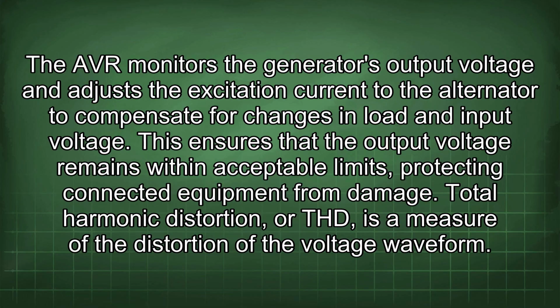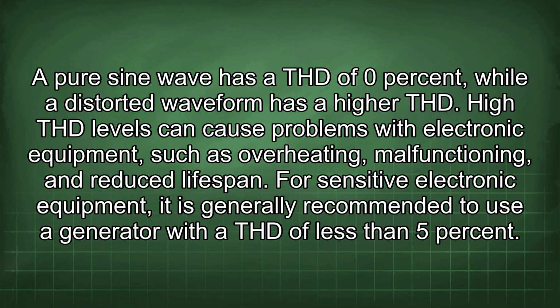This ensures that the output voltage remains within acceptable limits, protecting connected equipment from damage. Total harmonic distortion, or THD, is a measure of the distortion of the voltage waveform. A pure sine wave has a THD of 0%, while a distorted waveform has a higher THD. High THD levels can cause problems with electronic equipment, such as overheating, malfunctioning, and reduced lifespan. For sensitive electronic equipment, it is generally recommended to use a generator with a THD of less than 5%.